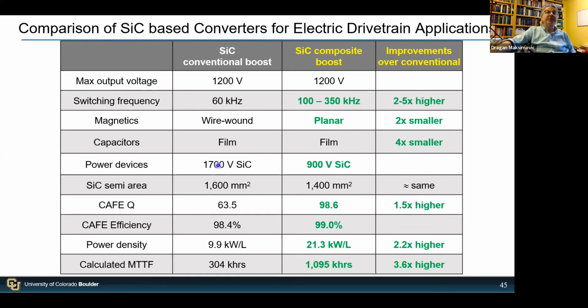The power devices here are 1700 volt silicon carbide and available 900 volt silicon carbide for the composite boost. You might say, well, you have so many more devices, but the total area of the devices in our system is actually smaller than in a classical boost—approximately the same, actually a little less. We have another 50% improvement in Q. The average efficiency is 99%, and the power density is another 2 times higher compared to the conventional silicon carbide based solution.